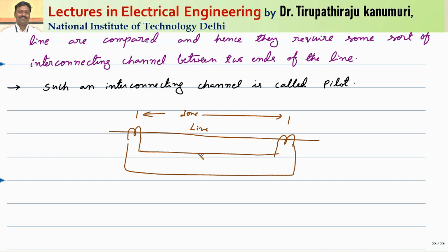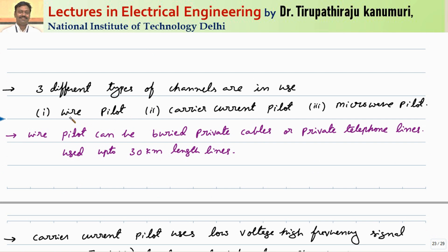Above 30 kilometers, we must go for wireless transmission schemes. One option is to transmit through the same transmission line using a different frequency compared to the supply frequency. Another option is to transmit using microwaves. So either we go for microwave transmission or carrier current transmission. Depending on this, there are three different categories: wire pilot, carrier current pilot, and microwave pilot.